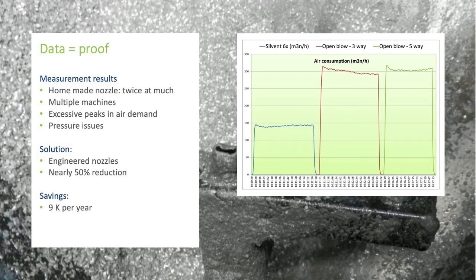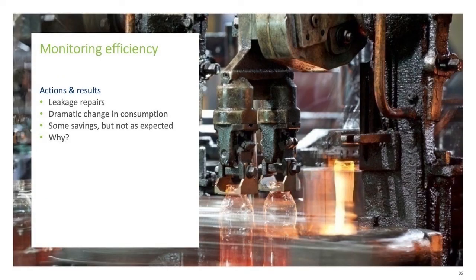Third example, this one I will talk about monitoring efficiency. Some large plants start very enthusiastically repairing the leaks, and this results in a dramatic change in consumption. But then the savings are not as expected if you look at the simple rules of thumb. So why is that? Well, the reason behind this is that as soon as you start to change and play around with the air demand, you're also shifting on the optimum curve of efficiency. And Bo already pointed it out in some of his very cool graphs.